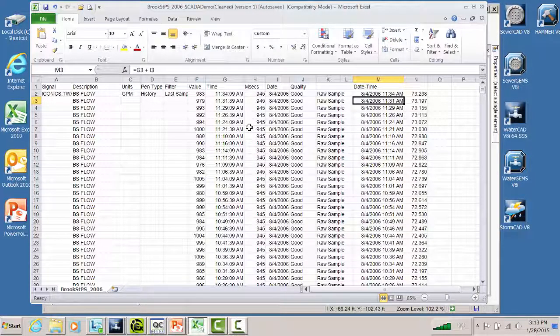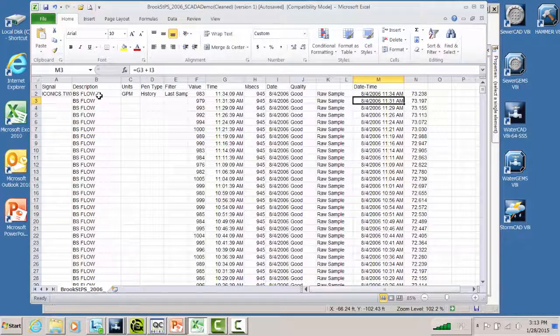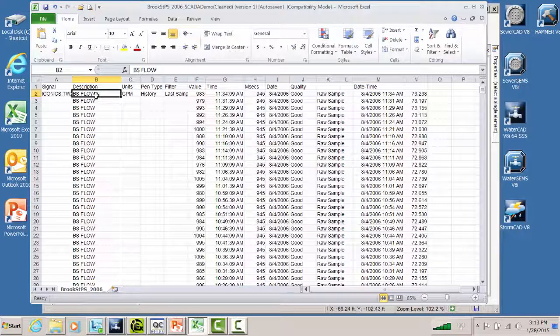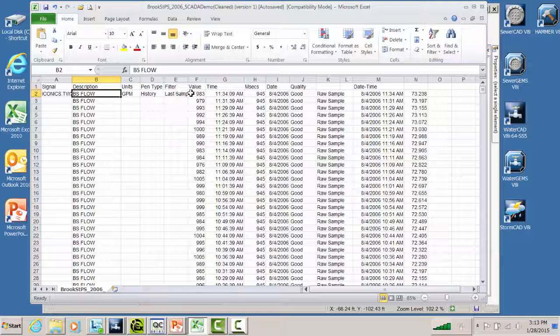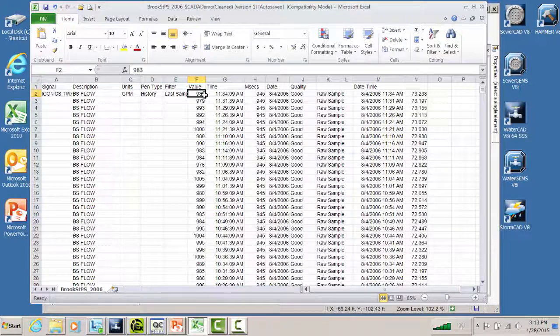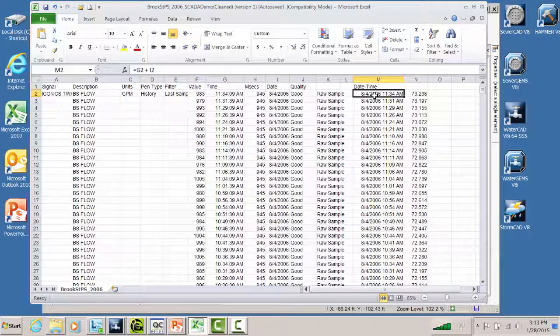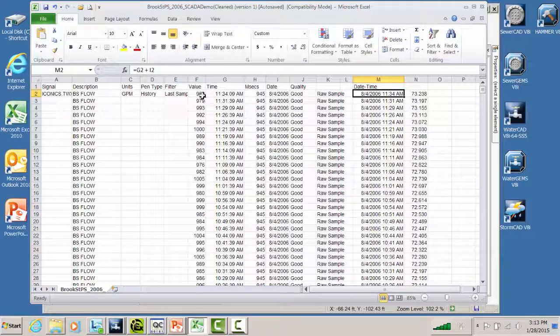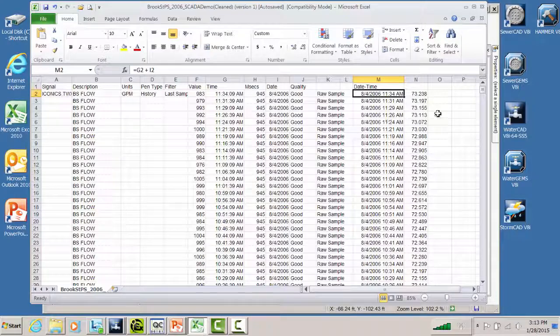So let's look at the kind of fields we'd be interested in. We need to know what the property is that we're plotting. We usually call tags in the SCADA system. What the numerical value is that has come in from the SCADA system. It's in the OPC server and it's downloaded to some kind of file, whether it's a spreadsheet or database. And then we look at the date and timestamp of this data. So that's what's of interest to us: date and time, the numerical value, and what property.